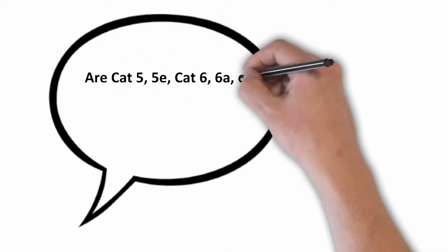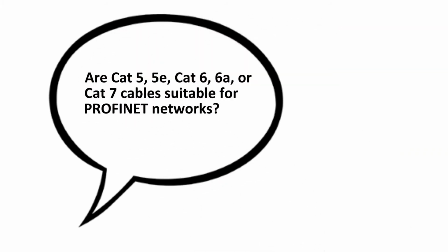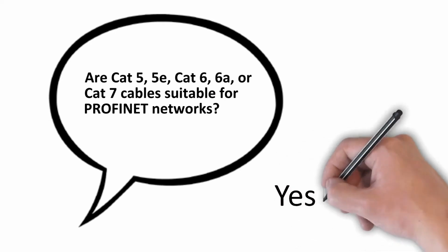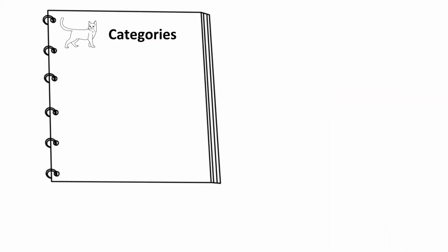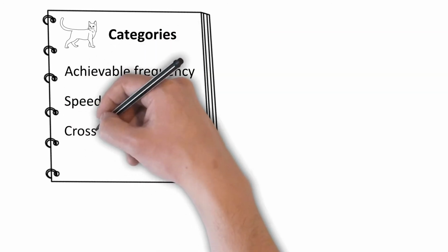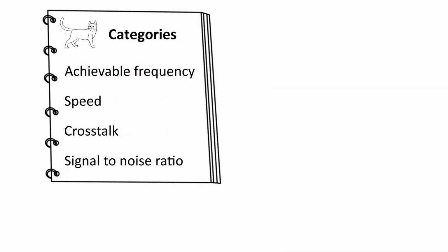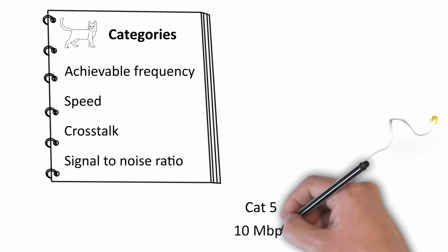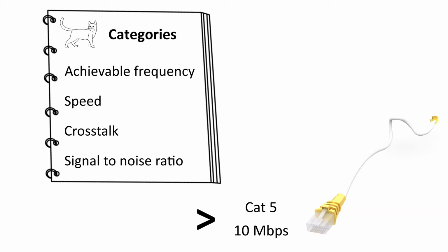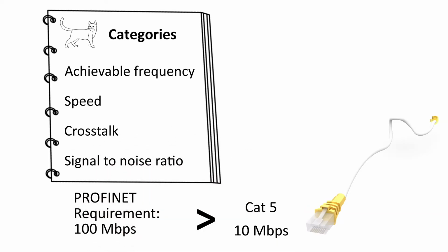A common question about copper cables in Profinet applications is if you can implement Cat5, 5e, Cat6, 6a, or Cat7 cables in Profinet networks. The short answer is yes, you can implement these cables. However, the categories only specify the performance of the cable, like achievable frequency, speed, crosstalk, and signal-to-noise ratio. You must also check the specifications of each cable. Some older Cat5 cables, for example, are unsuitable, as they are only capable of 10 megabit per second speeds, which is below the required 100 megabit per second for Profinet. That said, Cat5e is the most common, as it can fulfill the 100 megabit per second transmission speeds.